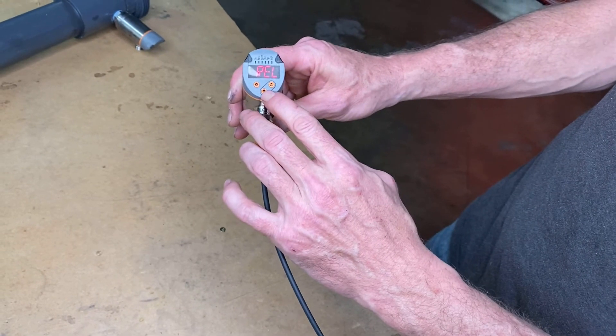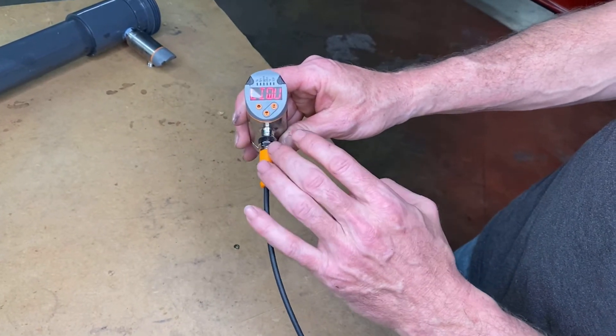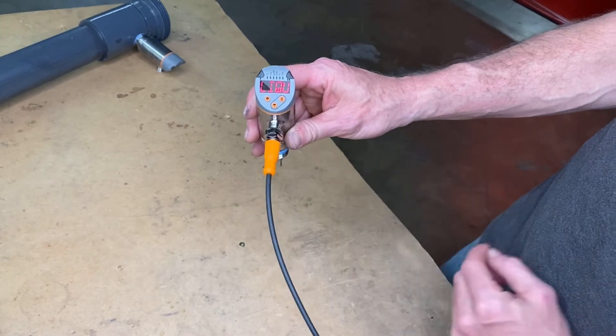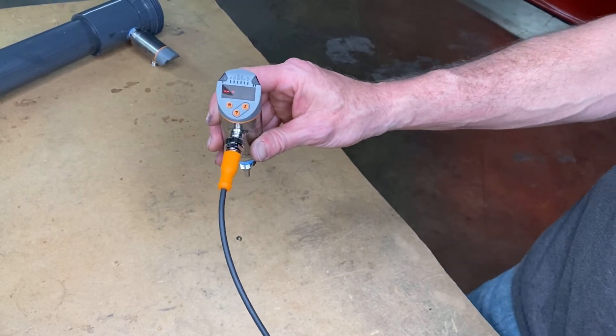Let's go to mode first. It shows REL, which means gas or water. To change this setting I hold the down button, and now I can switch between REL gas and liquid — we want to be on liquid. I'll hit the circle button and it's going to do a factory reset.